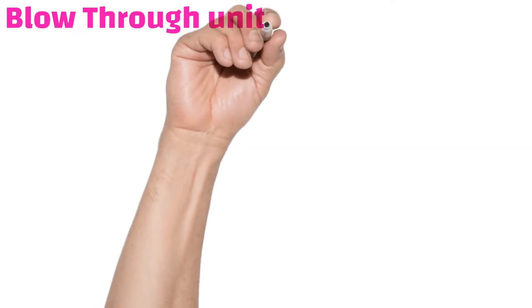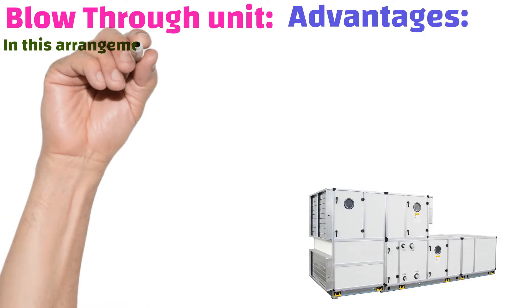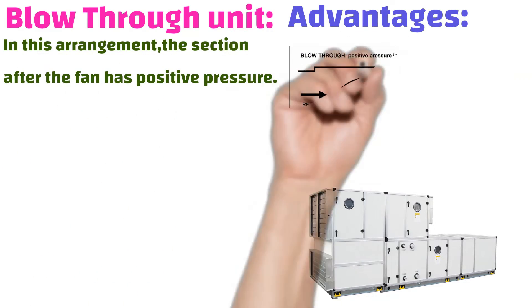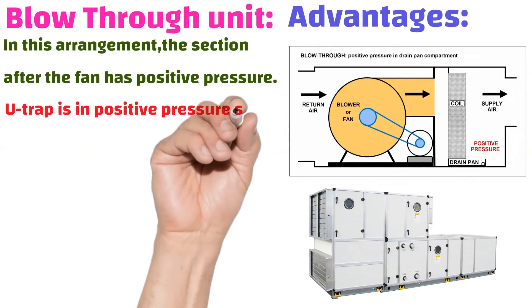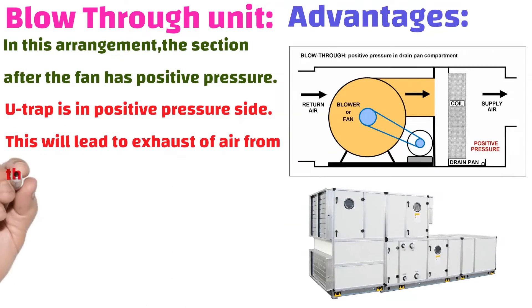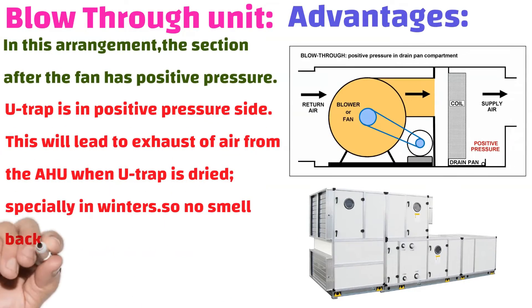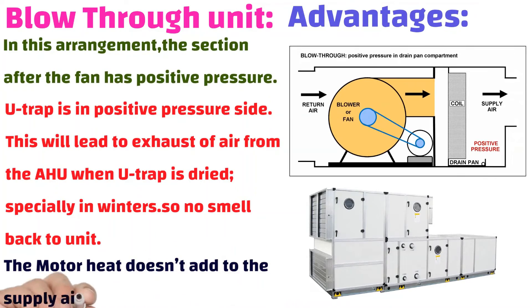Advantages of the blow through unit: In this arrangement, the section after the fan has positive pressure, so the U-trap is on the positive pressure side. This will lead to exhaust air from the AHU when the U-trap is dried, especially in winter. So there is no smell air returning back to the unit. The motor heat does not add to the supply air.